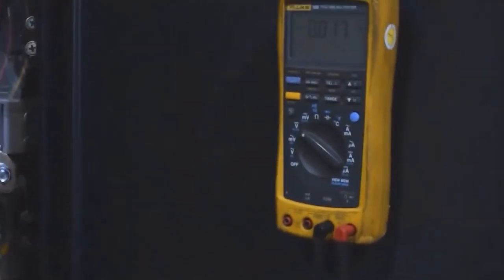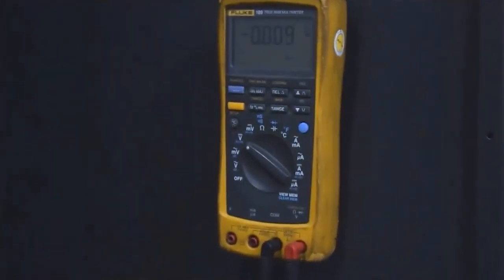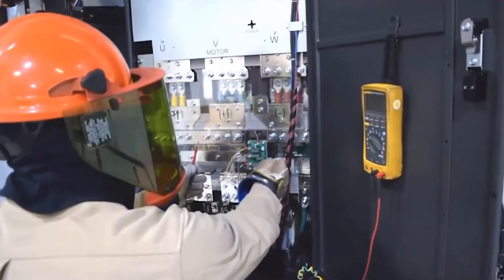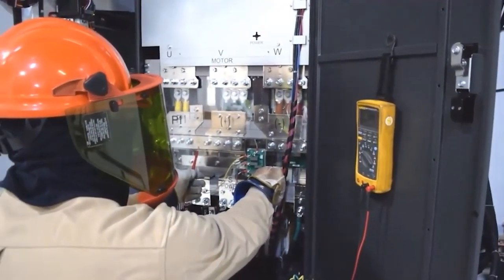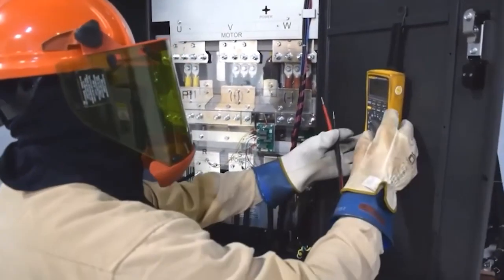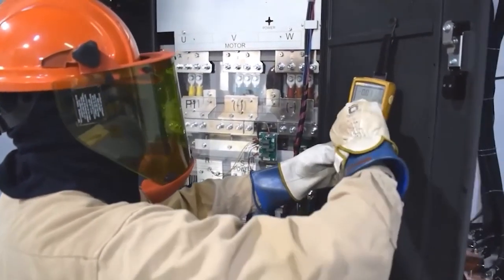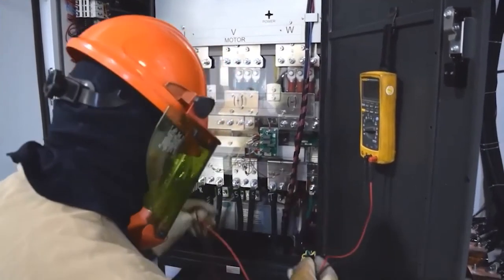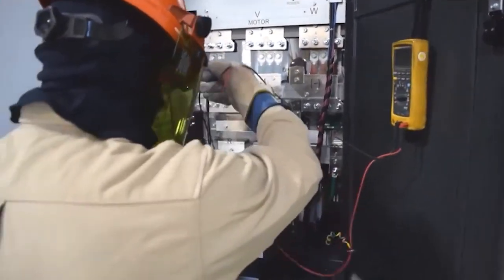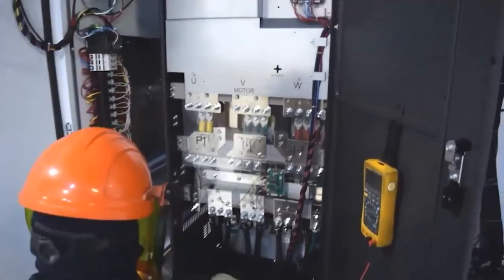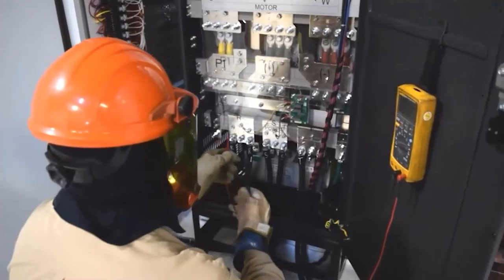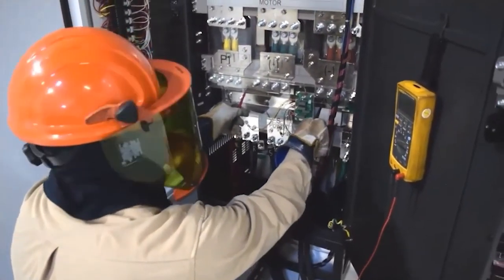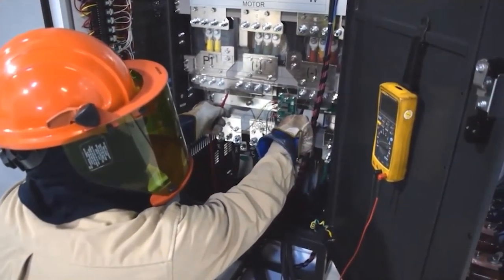Then after I've gone ahead and measured that, I'm going to move my meter to DC, and then I'm going to measure my DC bus. Now keep in mind, the DC bus is going to be between about 650 and 700 volts DC. And I'm going to measure it, make sure it all measures normally. I'm going to get my leads all tangled up. And then we're going to go ahead and take our reading.